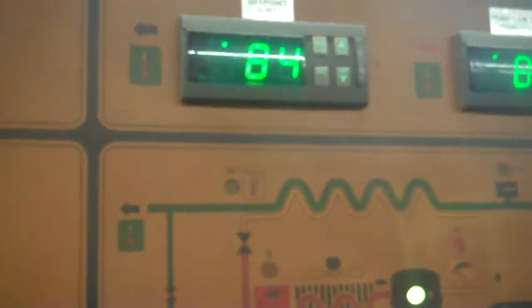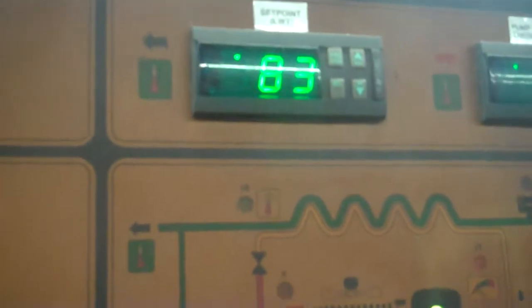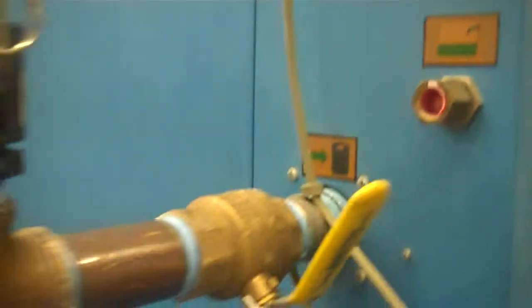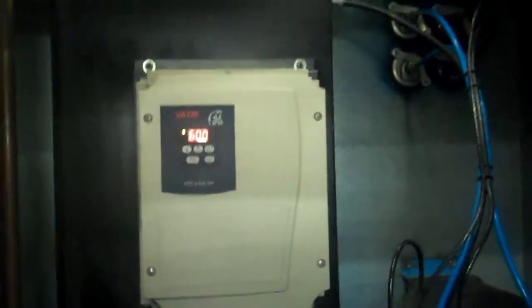So we're starting to chill right now. It's gotten down to 83. This is the inside of the unit. These water lines here are strictly from our heater to heat up the fluid in our tank for the test. Both fans are running right now. You can hear they're changing speeds a little bit, as they should. VFD drive.